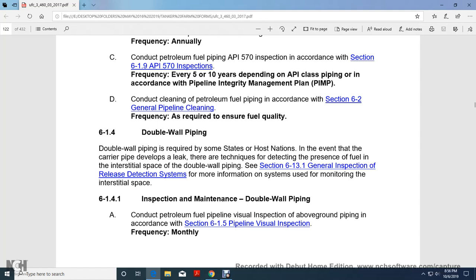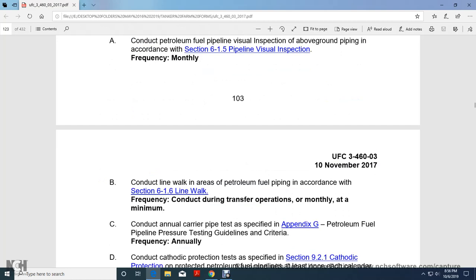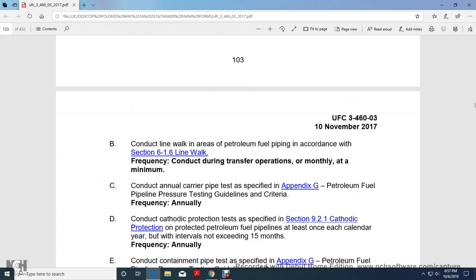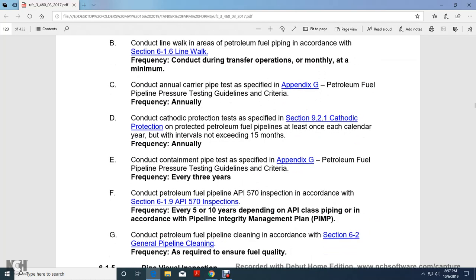Inspection and maintenance, double wall piping. Conduct the petroleum fuel pipeline visual inspection of above ground piping in accordance with 6.15, Pipeline Visual Inspection, frequency monthly. Conduct a line walk of the area of the petroleum fuel piping in accordance with 6.16, Line Walk frequency, at a minimum monthly. Conduct an annual carrier pipe test specified in Appendix G, Petroleum Fuel Pipeline Pressure Testing Guidelines, criteria frequency annually. Conduct a cathodic protection survey specified in 6.9.2.1, Cathodic Protection, for the protected petroleum fuel pipeline at least once each calendar year, at intervals not exceeding 15 months.